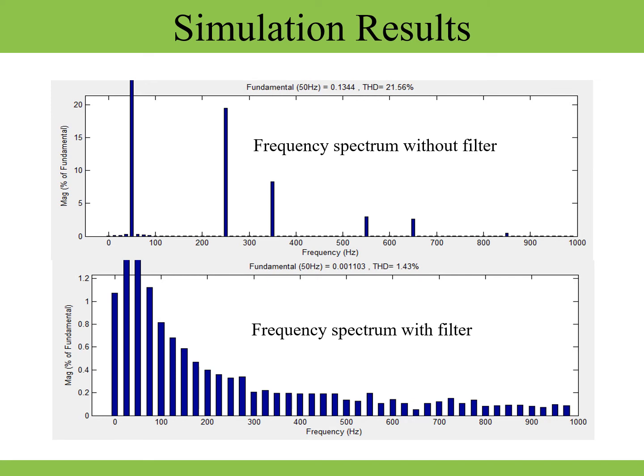The frequency spectrum is analyzed before and after introducing the active power filter. As we can see in the upper figure, the total harmonic distortion is about 21.56%, while in the lower figure the total harmonic distortion is 1.4%. The filter has significantly reduced the harmonics, as shown in the two figures.